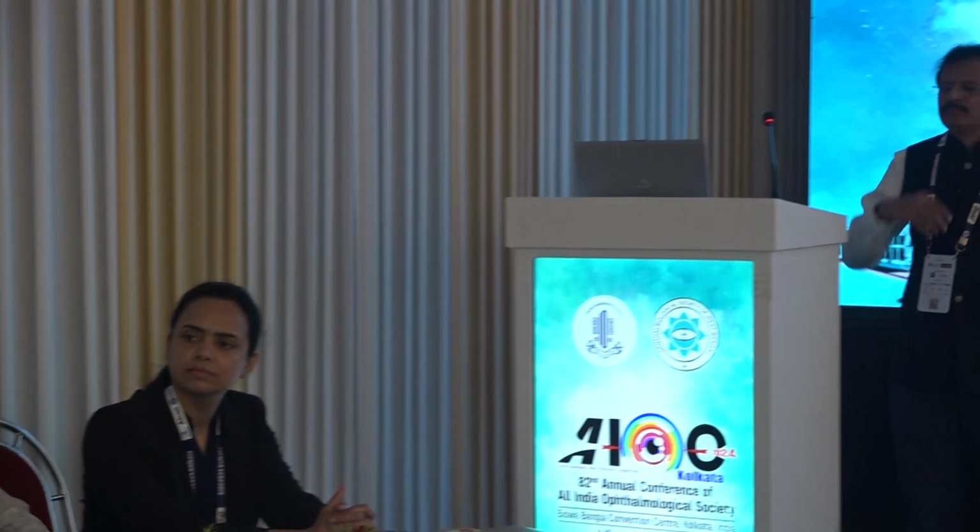Thank you, sir. Just a quick comment I want to make. Whenever you plan a C3R, after starting the machine, always calibrate it. It comes with a small calibrator, and you have to check that it is giving the proper intended power. Suppose you set the machine at 3 milliwatt, at a particular distance it should emit the same amount of power.